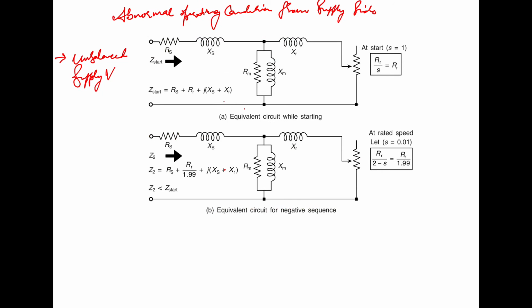Now, abnormal operating conditions from the supply side. An induction motor is subjected to many abnormal operating conditions as far as the electric supply is concerned. In some cases, quick disconnection of the motor may be needed, and in other cases, only an alarm may be sounded for an operator to take corrective action or to be ready for the shutdown.